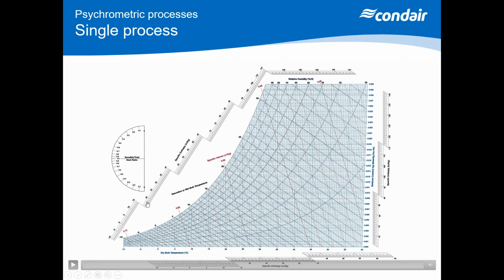So why do we have a dry bulb and a wet bulb temperature? Well, we have them because using those two temperatures determines other factors of conditions of the air. So it determines the moisture content, the relative humidity, the specific volume, and the specific enthalpy. By knowing those two temperatures, we can plot out all of those other conditions.